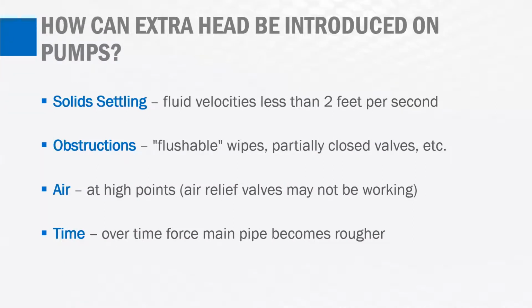So let's look at what can cause this extra head to be introduced on pumps. First, I think everyone's aware that wastewater has solids in it, and those solids can settle. 2 feet per second is the typical scouring velocity that's required in force main systems. It may be that initially the flow is such that you have that 2 feet per second of velocity in your line. Over time, things may change. You might have more head loss introduced, and that velocity could drop to less than 2 feet per second. Solid settling can be a concern in this case, especially on the lower parts of your force main.